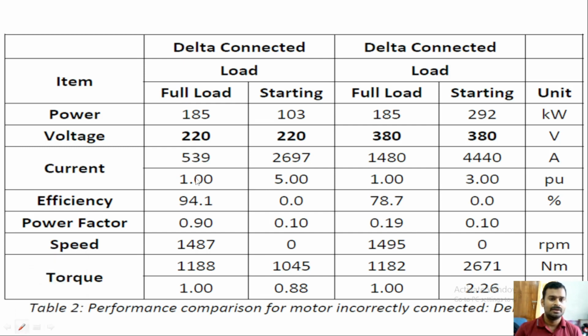Let us see here. For low voltage, delta connection should be there, so it is connected, and it is going to give appropriate performance, no problem. But here, instead of star connection, we have connected in delta. So what is going to happen? Certain things you can observe here. The torque, what is going to happen? The power, what is going to be, and remaining everything you can see here. The efficiency dropped from 94 to 78.7, and the power factor from 0.9 to 0.19. So you can see the difference. The power factor reduced from almost 0.9 to 0.2, and speed is almost okay, and torque is also almost okay, but the difference is with the efficiency and the power factor.